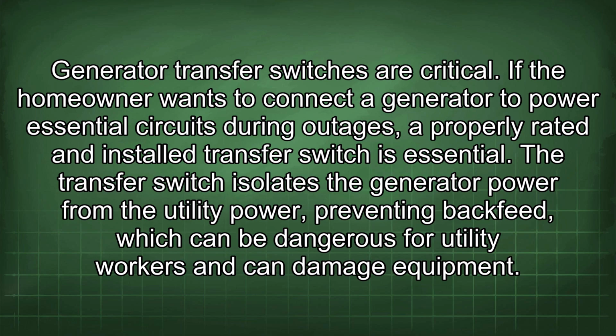If the homeowner wants to connect a generator to power essential circuits during outages, a properly rated and installed transfer switch is essential. The transfer switch isolates the generator power from the utility power, preventing backfeed, which can be dangerous for utility workers and can damage equipment.